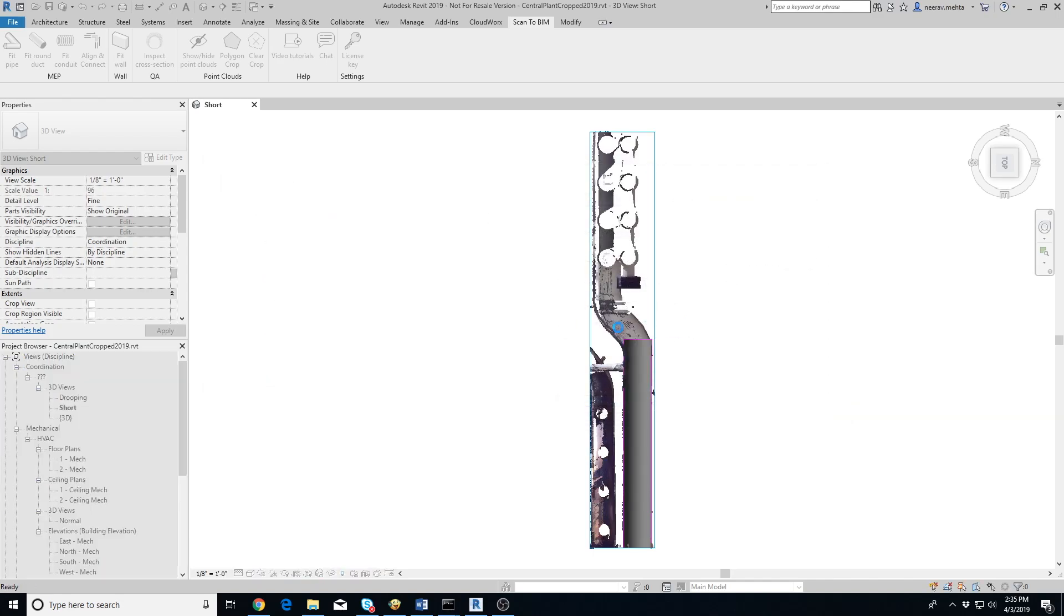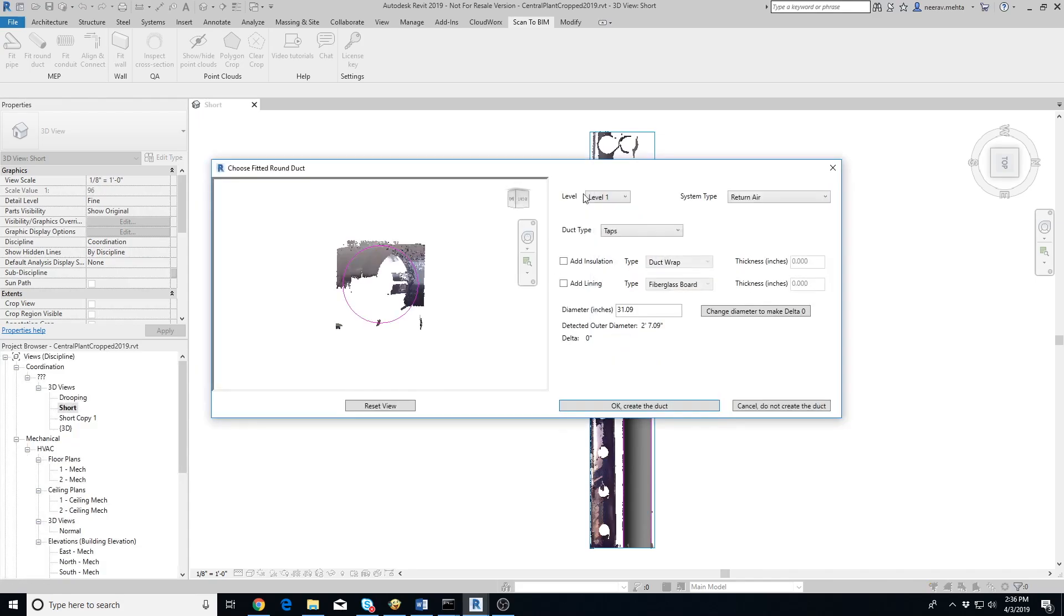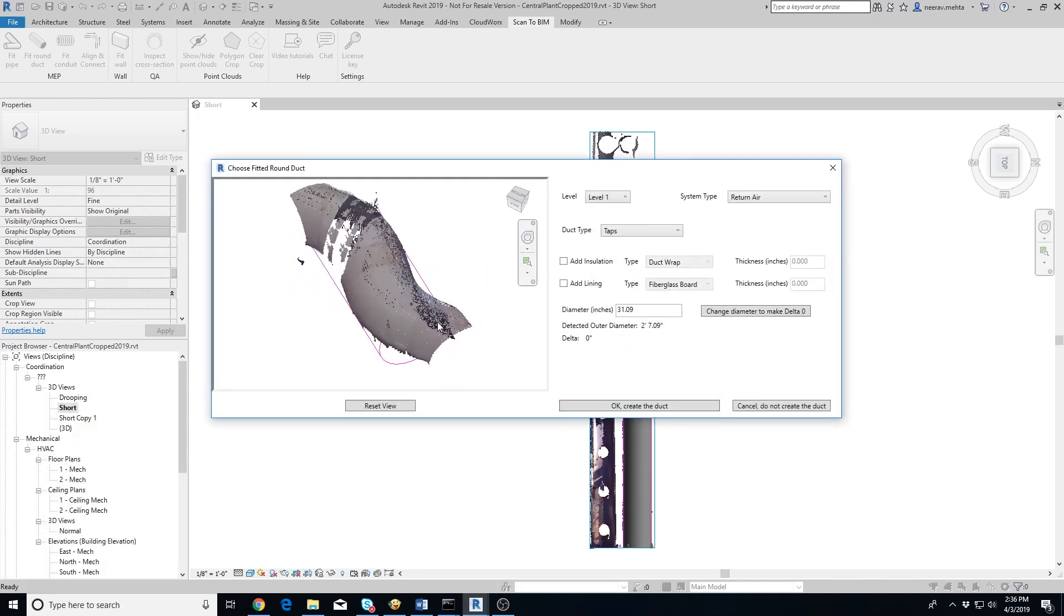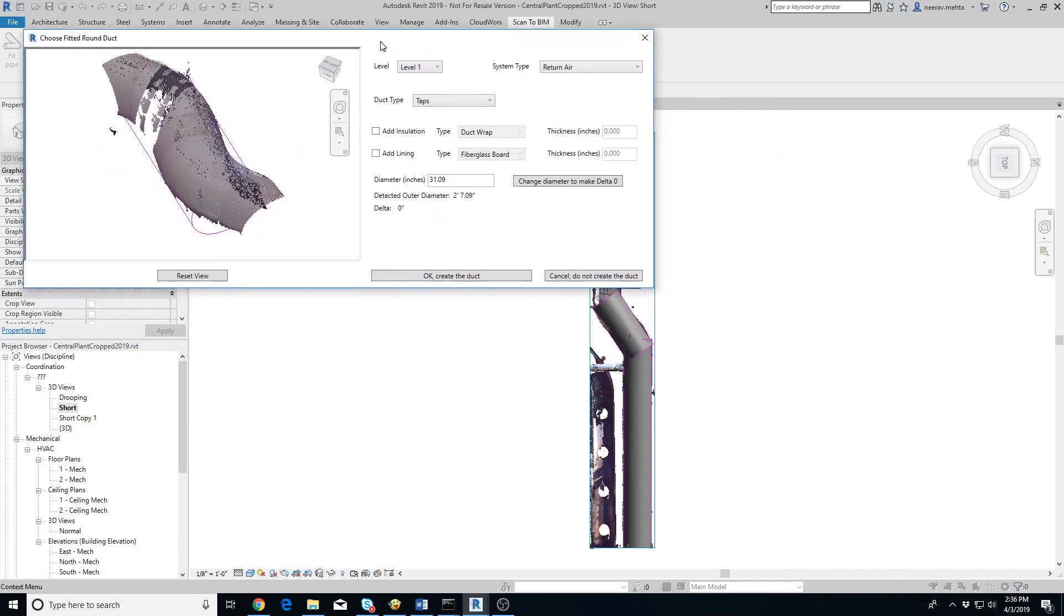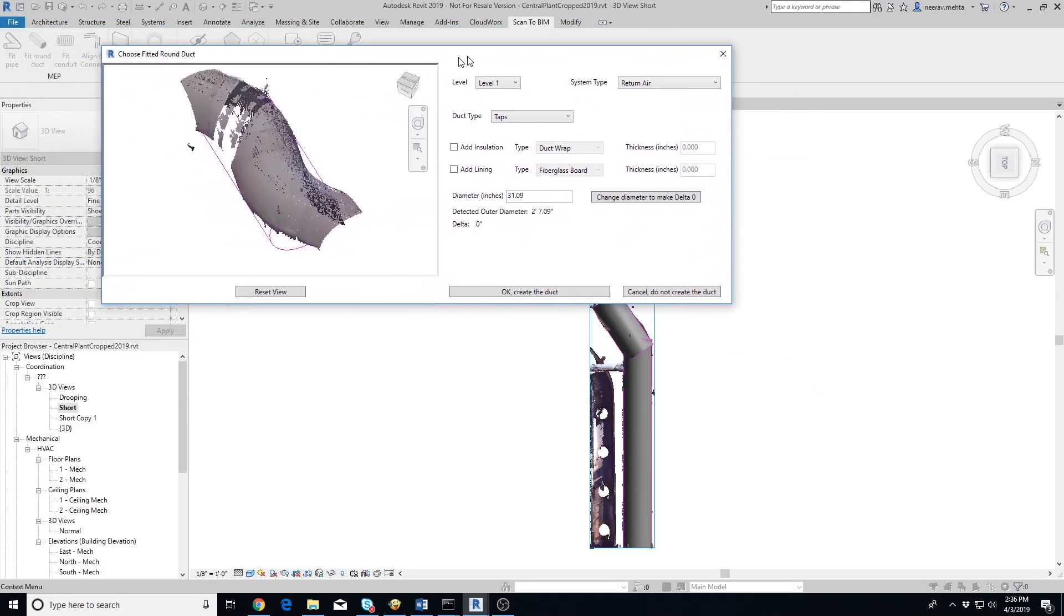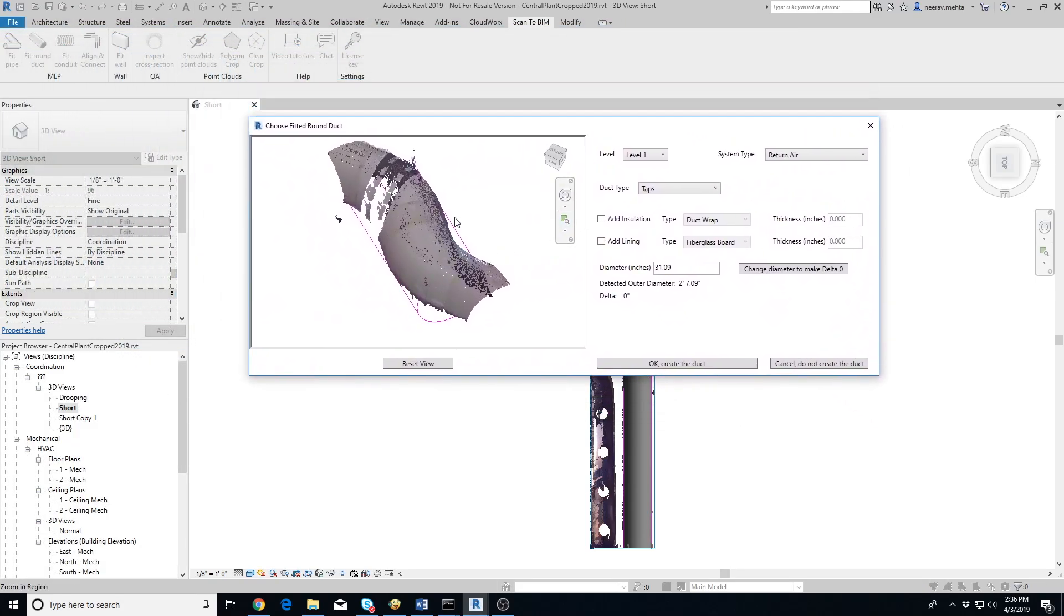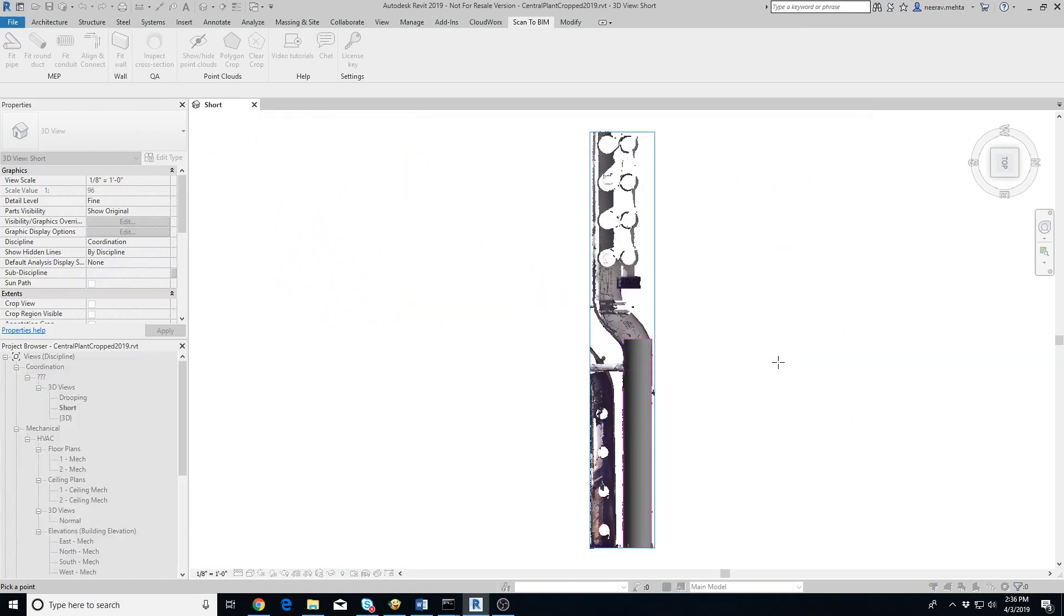Let's try extracting one more duct which is slightly more difficult for the add-in to extract. As you can see, the duct that the add-in extracted doesn't match the point cloud at all. In such cases where there are small ducts connecting two long ducts, it's possible for the add-in to get confused.